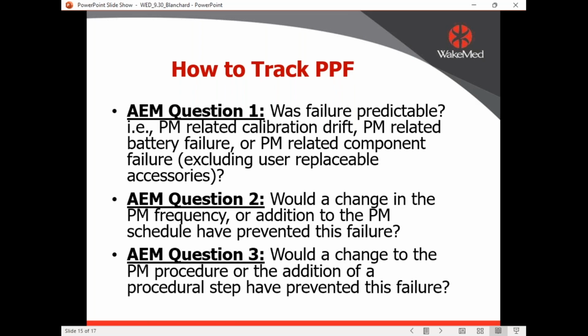Have not had an incident. I think we have 2,300 infusion pumps with no negative patient impact, and we've had those on AEM for 3 or 4 years now. So it saves a lot of time, because those PMs were, I think, 45 minutes on average. You have to run it for 20 minutes, and we never saw any fluctuation. They were accurate, so no need.